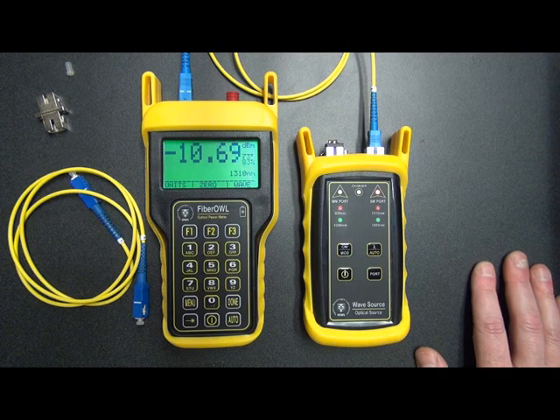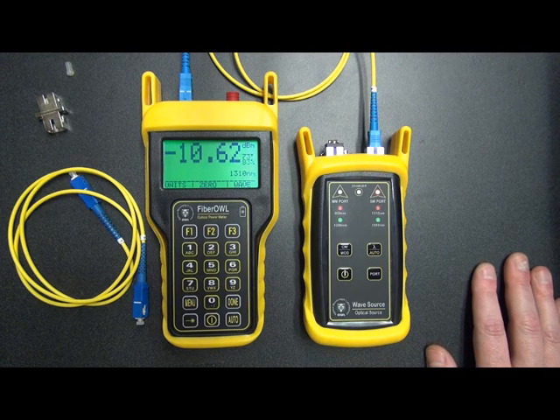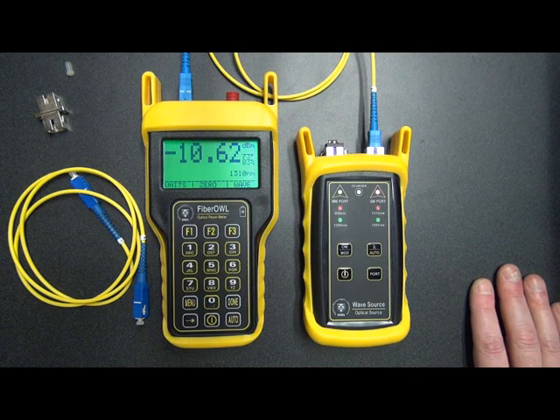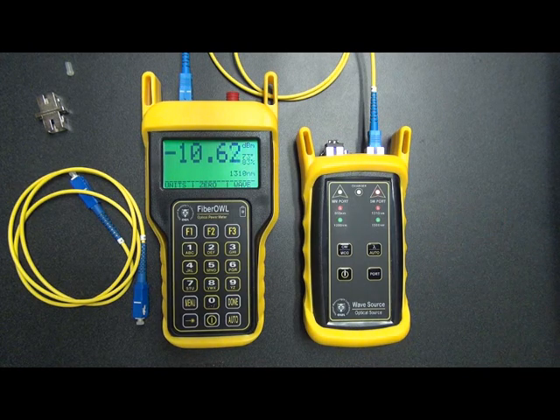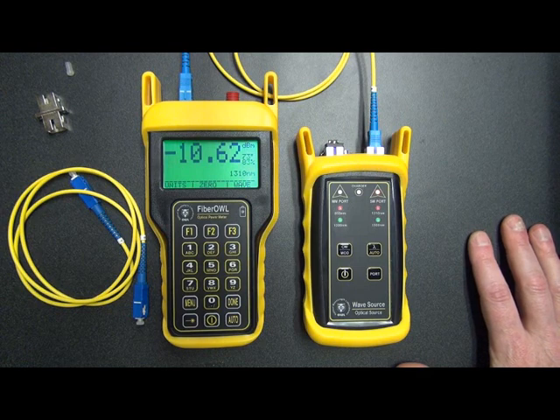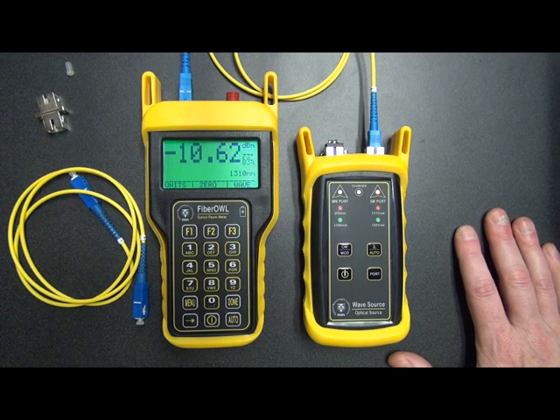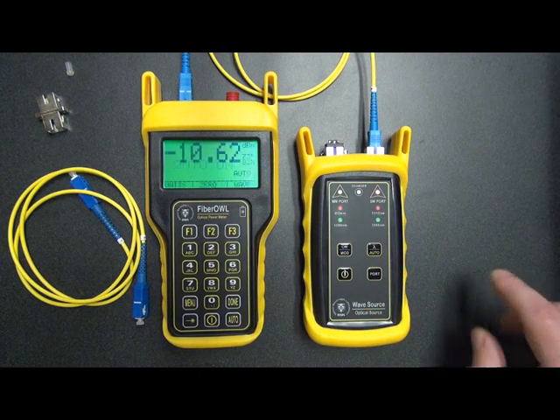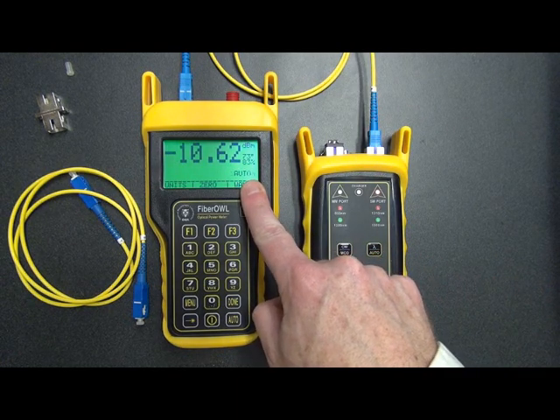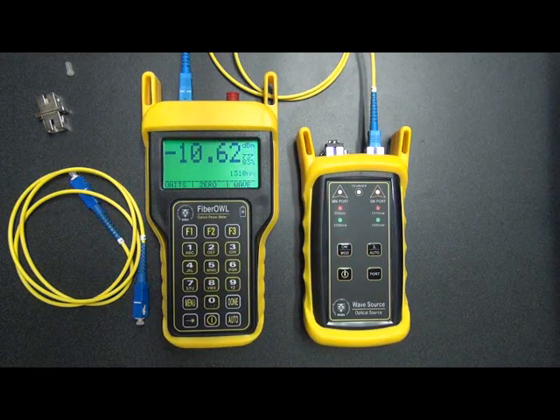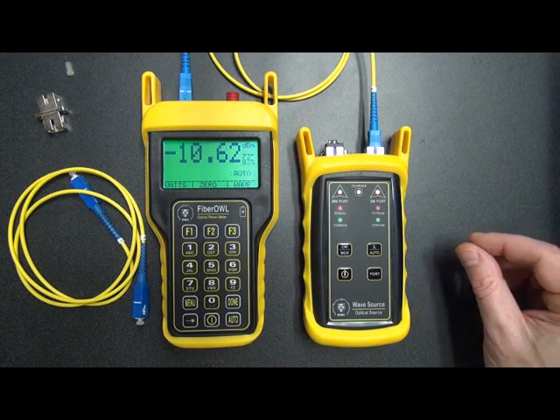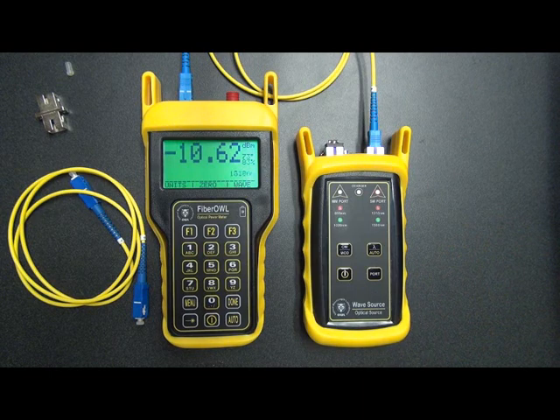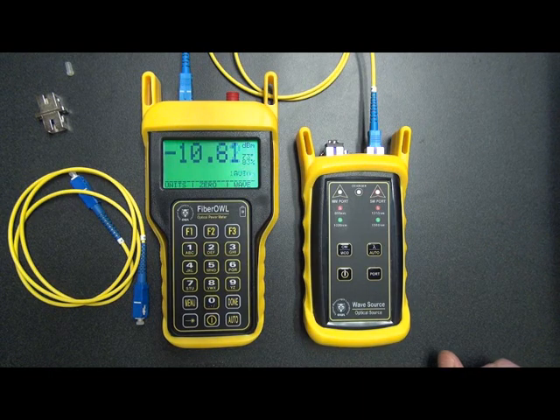It's also a good idea to check 1550 nanometers. So we would have to switch both units to 1550 nanometers to check that wavelength. But what I'd like to do here is demonstrate a nice feature of the Fiber Owl and the wave source when used together, and that's called auto mode. Auto mode allows the wavelengths to switch automatically. Simply done on the Fiber Owl by pressing the auto button. You'll see it says auto on. The wavelength indicator will now say 1310 auto and it will be switching back and forth between those two words. What this means is that the Fiber Owl is receiving light but it's not receiving an auto testing signal. It's just scanning incoming signals for auto, which it's not getting at this point.